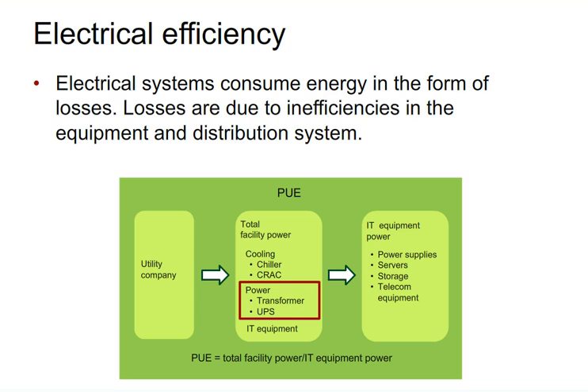Now turning to electrical efficiency. One of the key metrics in measuring efficiency in data centers is PUE — power utilization effectiveness, basically total power over IT power. When people look to lower their PUE, they generally look towards the cooling side. But the electrical system also consumes energy in the form of losses due to inefficiencies — the heat given off by the equipment on the distribution system.